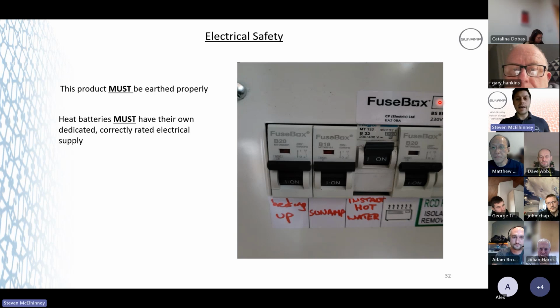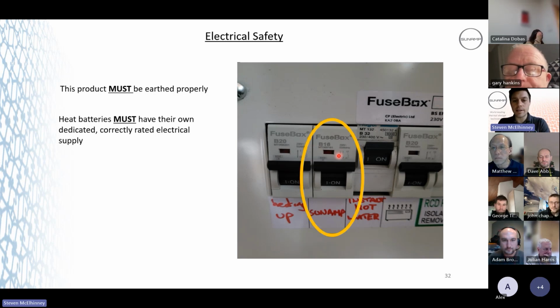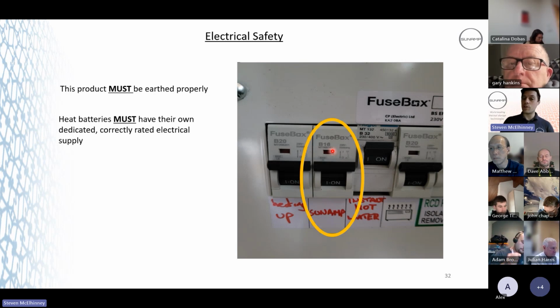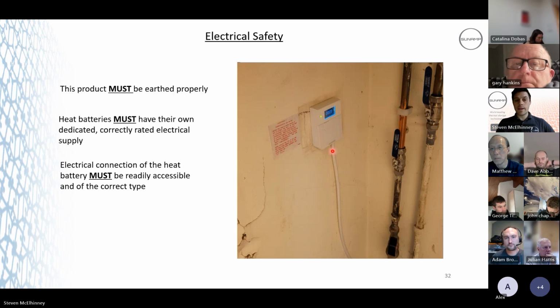No worries. The heat battery, you must have its own dedicated 16 amp breaker back at the fuse board, and then obviously you have to investigate, is the twin and earth the right size? So you should have your dedicated 16 amp supply, and then run it in 2.5 mil twin and earth from the fuse board to your double pole isolator where the battery's going to go.